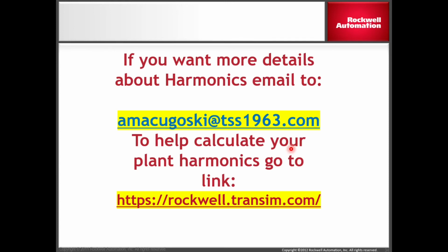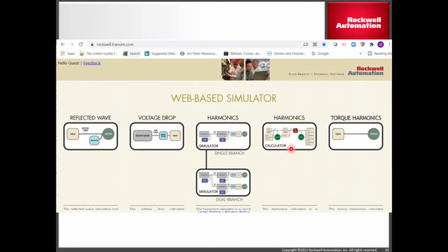So if you want more details about harmonics, send me an email and I'll send you out a PowerPoint that goes over it even further. If you need help in calculating what harmonics might be in your plant now and how you might mitigate them, Rockwell has a website, and there the link is below, which brings you to their web-based simulator. So you can calculate the harmonics, you could add filters, remove filters, add linear loads, take linear loads out, etc. to help determine what and if you need to reduce harmonics in your plant.